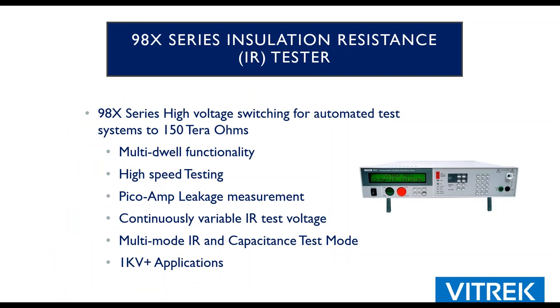All right, so this is a newer product. We leverage some of the 95X infrastructure to make a lower noise, very high accuracy, and high voltage tera-ohm meter. So most IR meters out there are going to stop at 1,000 volts. You know, you're going to have 500 or 1,000 volts, and that was fine. But we were constantly running across applications that are higher and higher in voltage. And now we can offer a solution for very high precision. You know, typically this is going to be used for 100 gig ohm requirements or more, up to 10,000 volts.